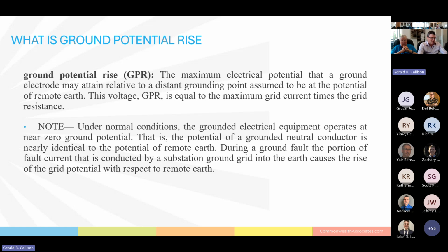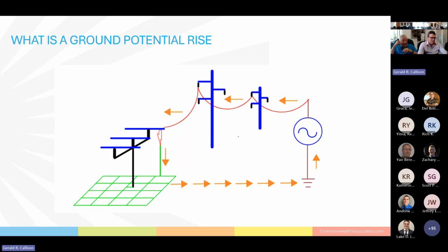Let's look at a picture and see what ground potential rise actually is. Here we see a picture of a very simple grounding system. We see a remote source providing ground current through a transmission line into a station bus that has a single line to ground fault, providing fault current into a ground grid, which is buried in the soil. This ground current then leaves the ground grid through the grid to soil interface and travels through the soil back to remote Earth. There is a resistance between this ground grid and remote Earth, and that's the resistance of the ground grid.